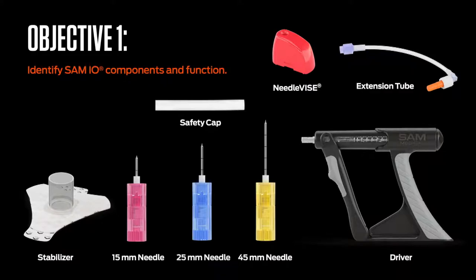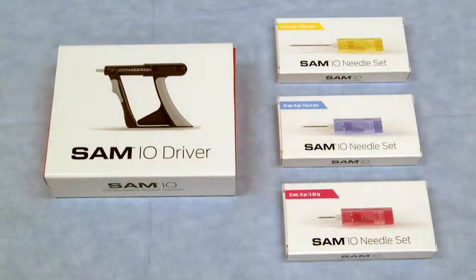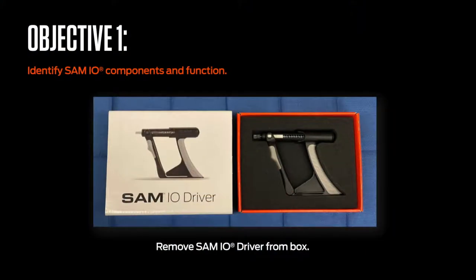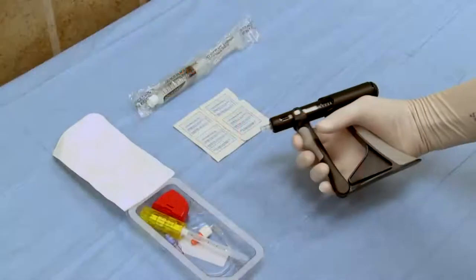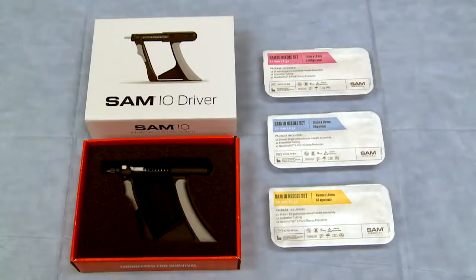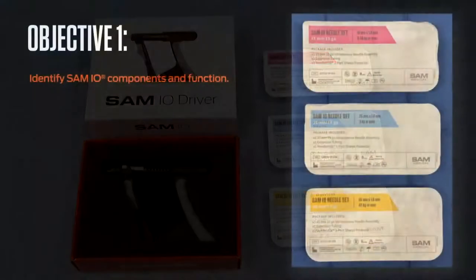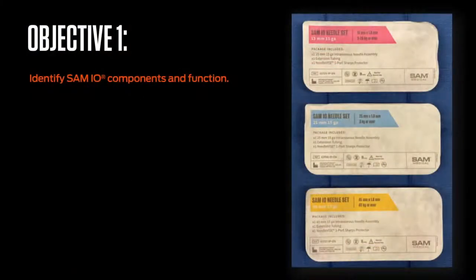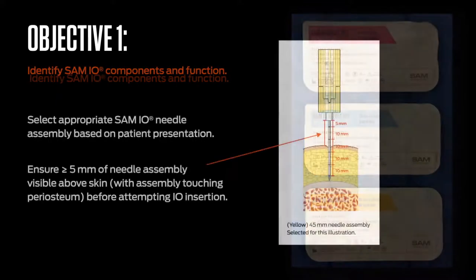No PPE or cleansing agent is supplied with the SAM.IO. The SAM.IO driver, which is reusable, can initially be found in its supplied packaging. Remove the driver from its packaging and repeatedly compress the driver's assembly to appreciate its unique function. SAM.IO needle assemblies are provided sterile in color-coded, size-specific, labeled packaging. Standard sizes include a pink 15 mm 15 gauge needle assembly, a blue 25 mm 15 gauge needle assembly, and a yellow 45 mm 15 gauge needle assembly.